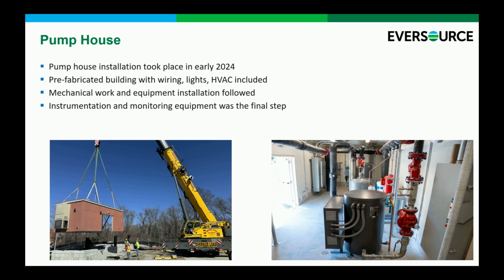We've got a backup boiler that you can see there in the front of that photo on the right, and we've got that large 800 amp disconnect that's on the wall back there on the left. But otherwise, we're mostly just pumping water through the neighborhood. We've got another set of pumps that run down through the bore field that is adjacent to this pump house. But at its heart, it's very, very simple, which means it's very easy to maintain and very easy to monitor.